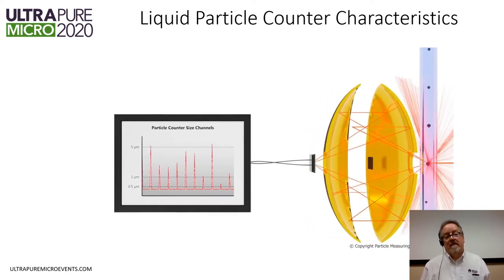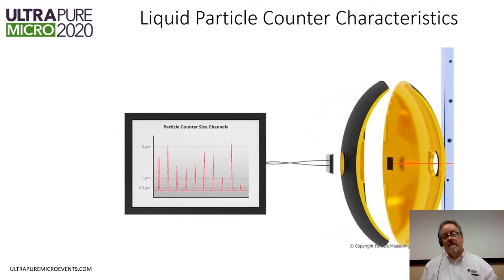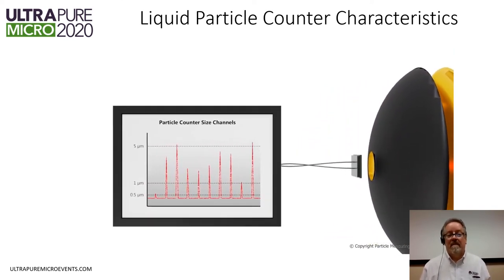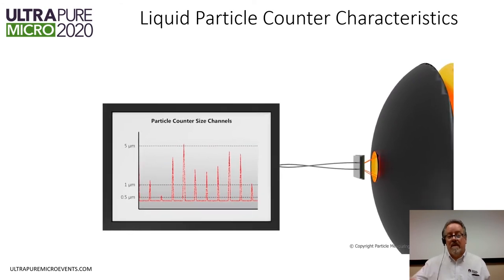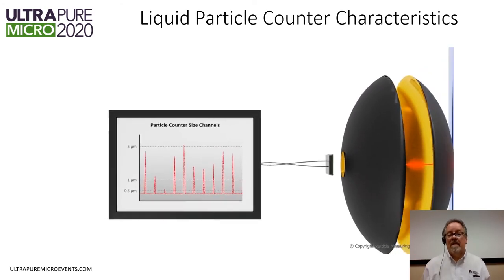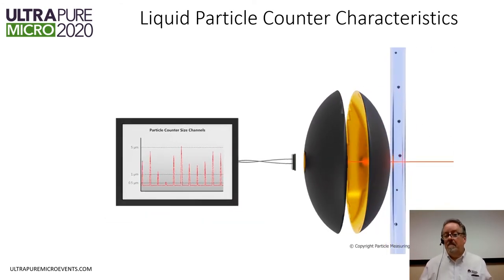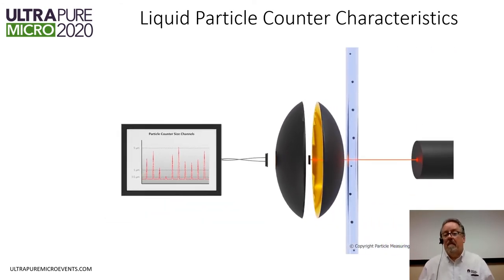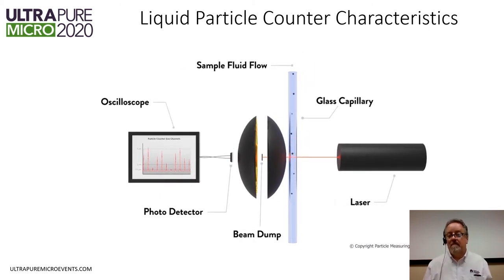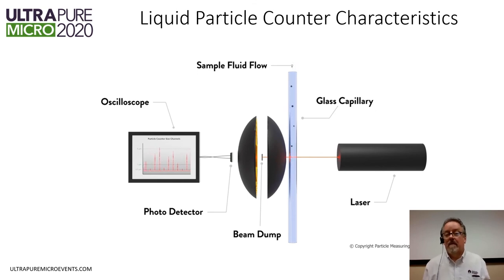We can look at that over here on the left, where the signal in millivolts equivalent is on the vertical scale. Every time a particle passes through, it creates a spike in signal, and we can bin those by particle size — we know how many particles in each size pass through the laser beam. These are typical of any liquid particle counter.